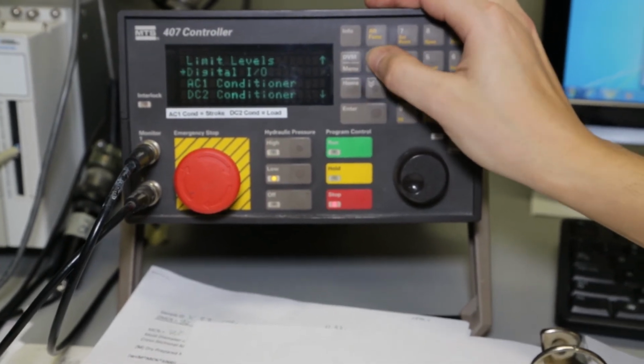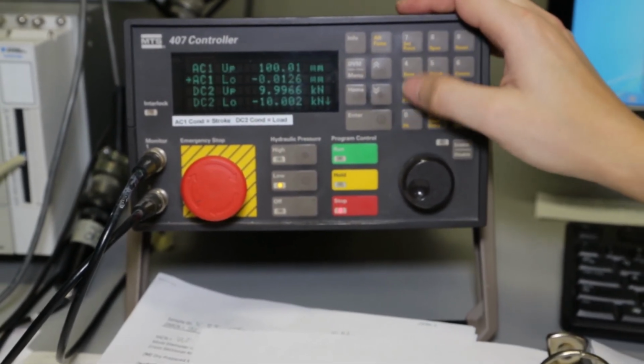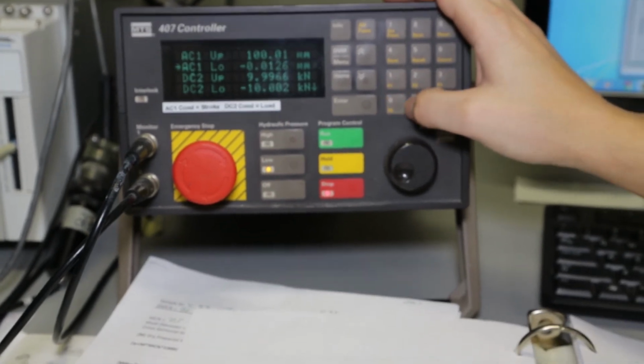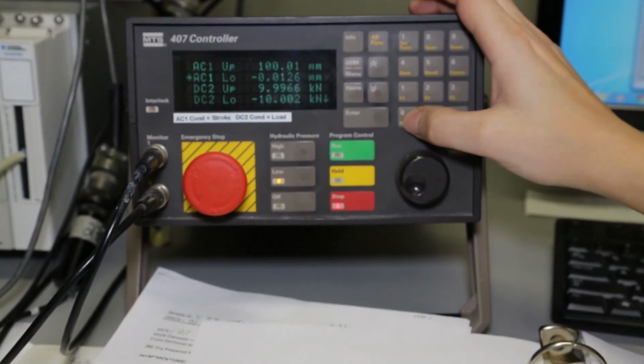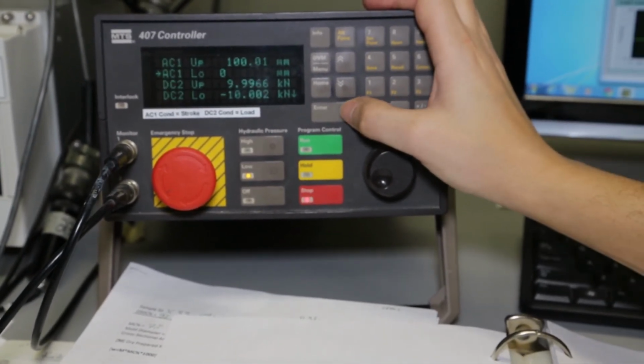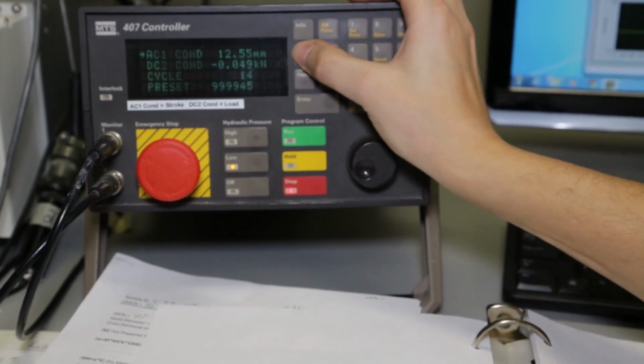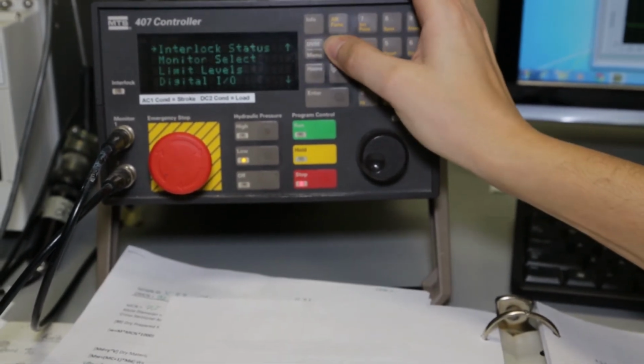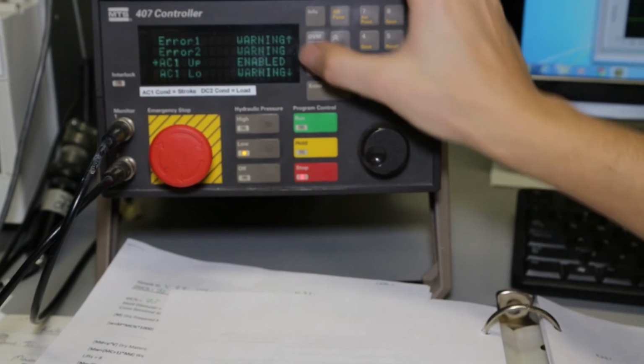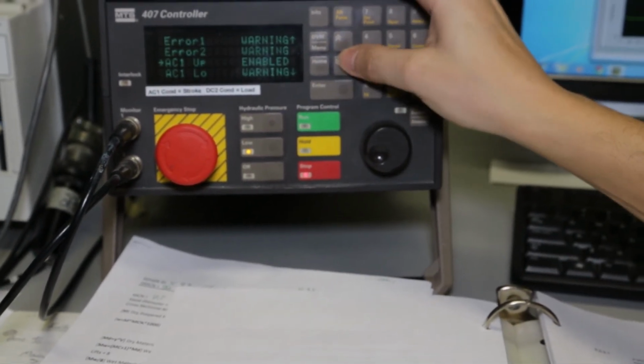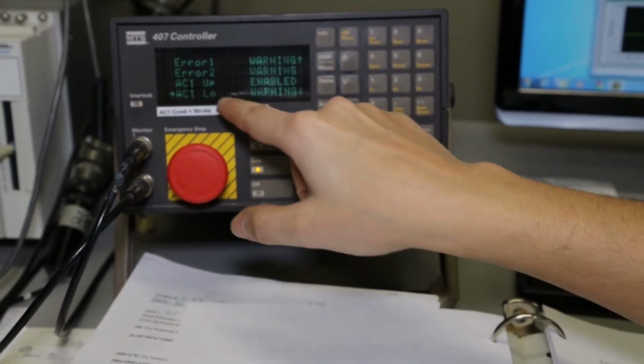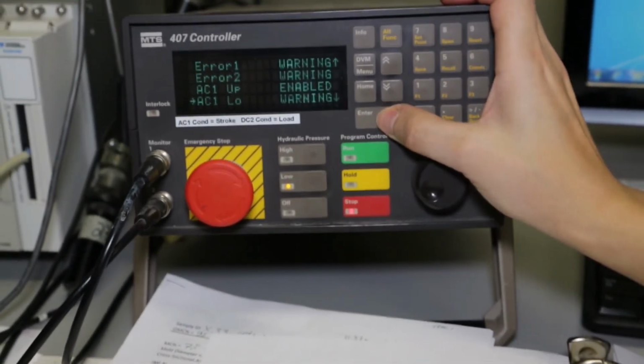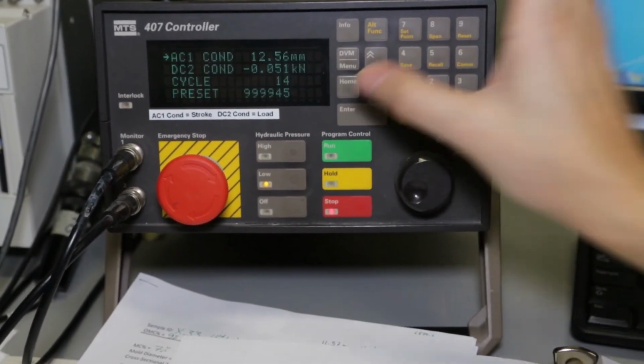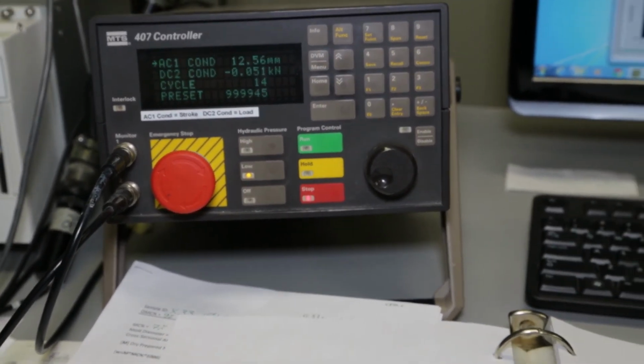I go to limit levels. 12 minus 10 is 2 millimeters, but just to give it a little more room, I set it on 0 right now. And then go back to interlock status. I disabled it earlier to allow the piston to go up. Now I put it on enable, and then everything is set.